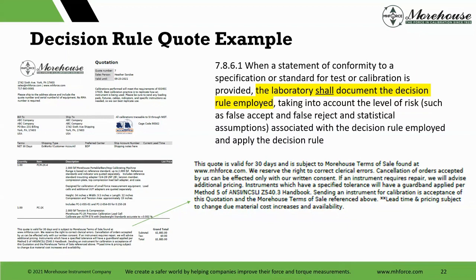If it's just, hey, just do what you want to do and provide it, by default, we use method 5. And we say that right there in this language, that we use method 5 of the handbook. So you send us a force gauge, a load cell, a crane scale, anything with an accuracy specification, we're going to calculate that calibration process uncertainty that we're going to talk about, and we're going to use method 5. Now, if you want other rules, we can discuss them.